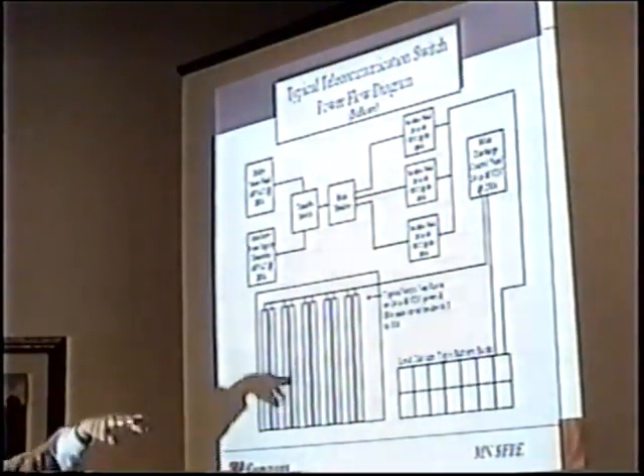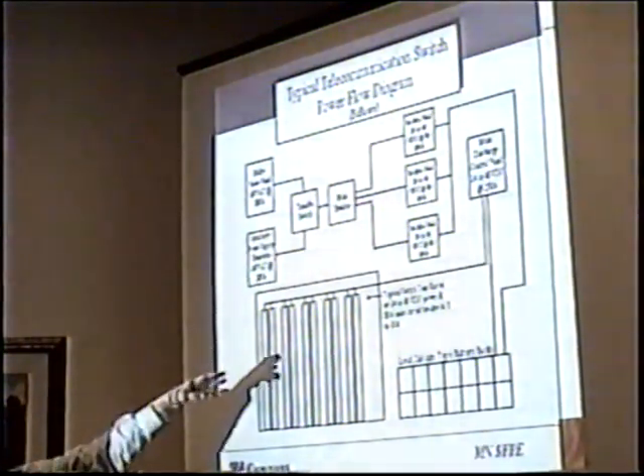That then goes directly to the battery pack, and it continually charges that battery pack, and then goes into the main discharge control panel, from which it goes into the switch. And then that is further broken down, again, all 24 or 48 volt DC. There are breakers from anywhere from 30 amps on down.